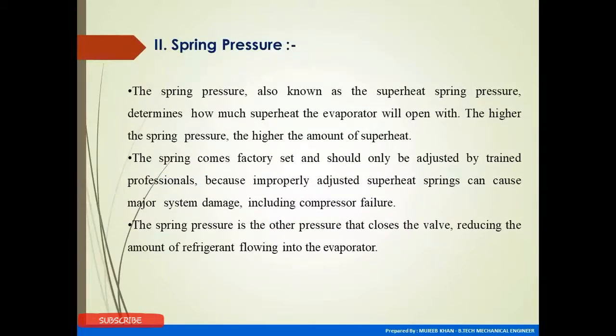The spring pressure, also known as the superheat spring pressure, determines how much superheat the evaporator will operate at. The higher the spring pressure, the higher the amount of superheat. The spring comes factory set and should only be adjusted by a trained professional, because improperly adjusting the superheat spring can cause major system damage, including compressor failure. The spring pressure is the other pressure that closes the valve, reducing the amount of refrigerant flowing into the evaporator. It is essential that it be handled only by a trained, qualified technician.